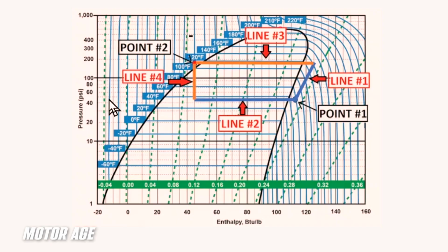So the first thing you have to keep in mind here is pressure, shown vertically on the left side of this chart. It's drawn here in pounds per square inch, but what you need to know is this is represented in absolute pressure. So if we are reading a gauge and it reads 0 psi, and for instance I was at sea level, I would have to add approximately 14 to 15 pounds to my reading. So if I had gauge pressure, I'd have to draw on the chart an additional 15 pounds. Again, just something you need to keep in mind. As I mentioned earlier, the numbers on the bottom of the scale are something we're not going to use. That's enthalpy. But we are going to use these green lines that are radiating outwards from these green numbers here to act as a visual point of reference.